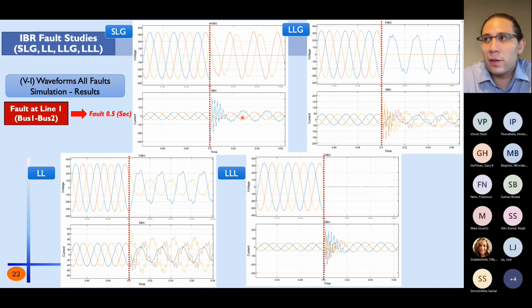For the people who have experience with faults and protections, we know that the fault current is usually 7 times the nominal, and it's actually very big and it's easy to detect. But due to the power electronics side and the limiters for protecting them, we don't see those waveforms in the inverter integration. That's what makes it challenging to detect the traditional way. Additionally to the cases where I showed before that they do affect directly.